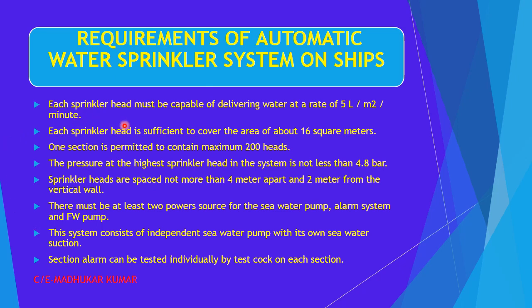Each sprinkler head must be capable of delivering water at the rate of 5 liters per square meter per minute. Each sprinkler head is sufficient to cover an area of about 16 square meters. One section is permitted to contain a maximum of 200 heads. The pressure at the highest sprinkler head in the system is not less than 4.8 bar. The sprinkler heads are spaced not more than 4 meters apart and 2 meters from the vertical wall. These are the SOLAS guidelines.